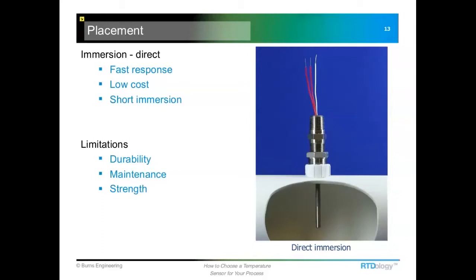These are going to give you a fairly fast response with the direct immersion style. Again, fairly low cost, and we can get away with a pretty short immersion length. If we had a really high flow rate in this pipe, durability could be an issue. Certainly maintenance is an issue, because we have to shut down the process, drain the piping, and then pull the sensor out and maybe calibrate or replace it, whatever the case may be, and then start the process up again.